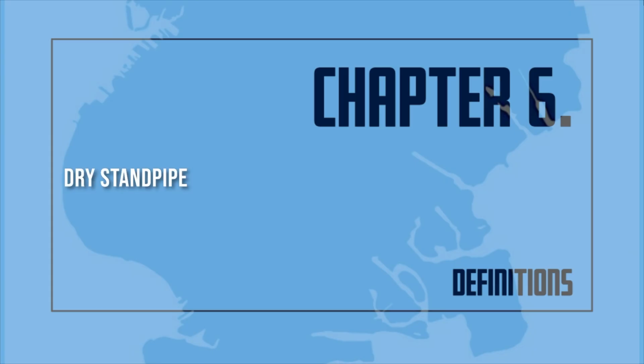Dry standpipe, a standpipe system designed to have piping containing water only when the system is being utilized. Manual dry standpipe, a dry standpipe system without an automatic water supply. This system requires the connection of fire department apparatus via the fire department connection for operation. Automatic dry standpipe. A dry standpipe system that is supplied by an automatic water supply. A dry or deluge valve is used to maintain the system without water until it is needed for firefighting purposes.